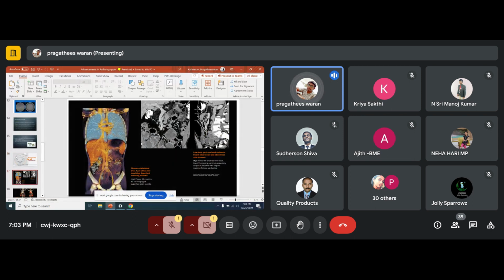Here I want to explain: dual source is different, dual energy is different. This is an example of dual energy. Even if you are scanning particular studies like kidney stone studies or calcium related studies, it won't be that clear in normal CT scans. Again I'm reiterating, dual energy is different, dual source is different. Dual source CT scanner means two tubes will come, whereas dual energy means a single tube will expose at two different energies, and by subtracting, we will get the information we require.